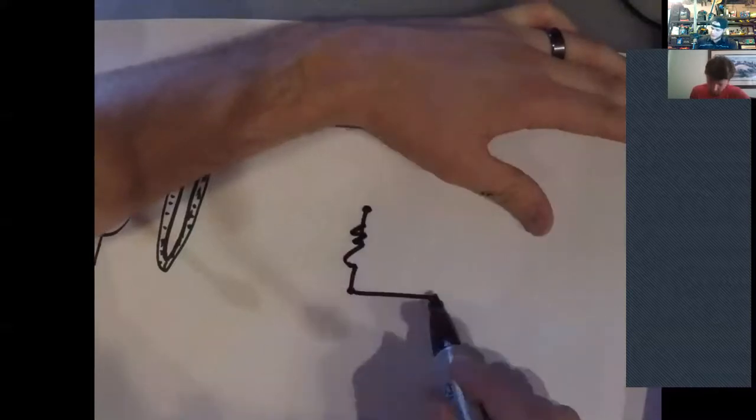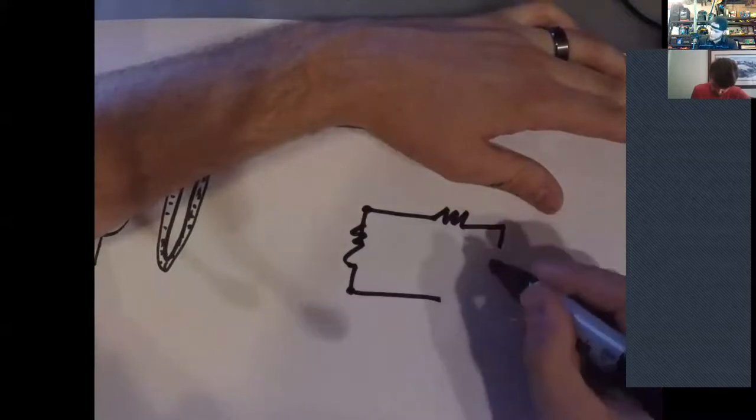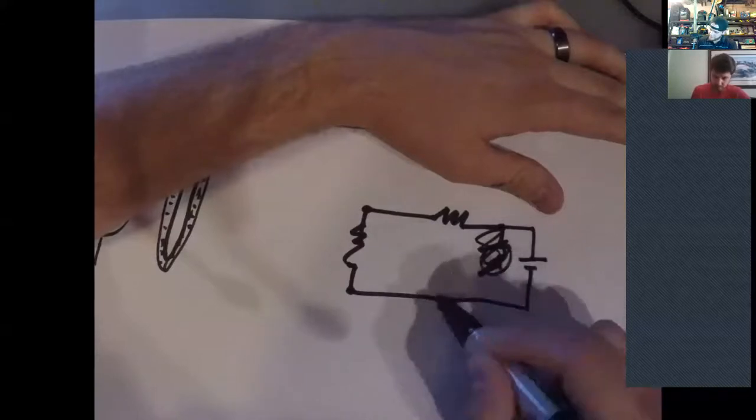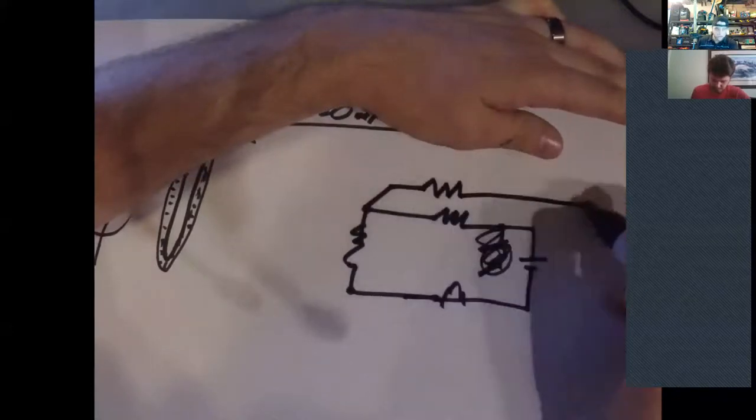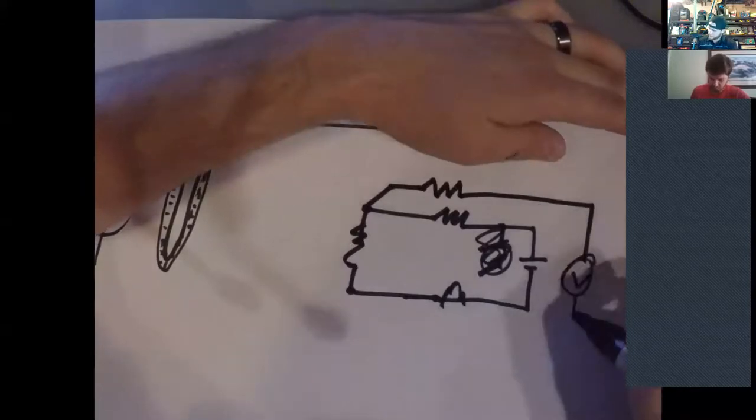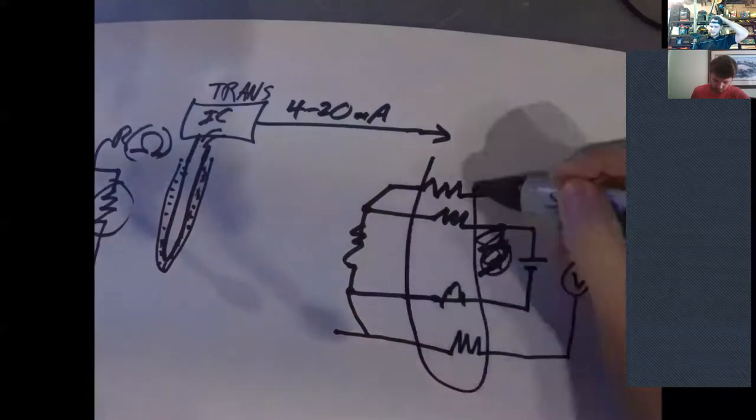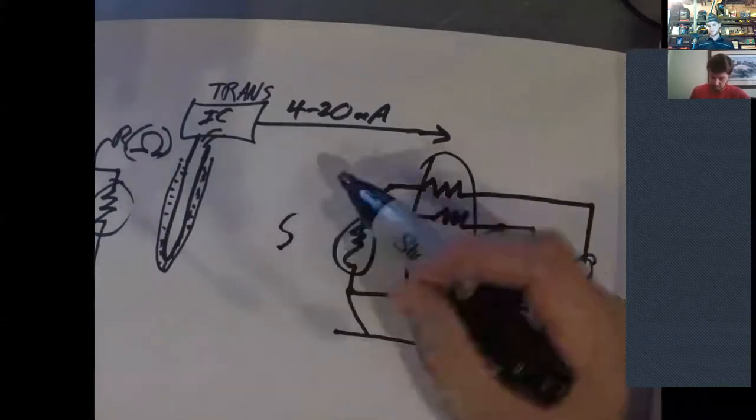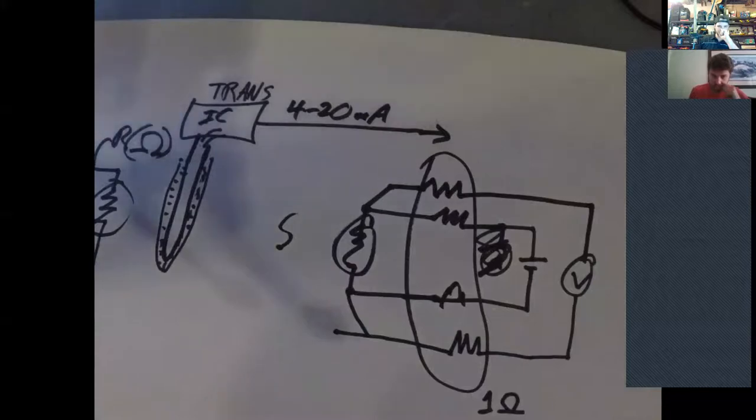Exactly. Voltage drop. So you have an inherent resistance in your wires. And so if your wire length is really long, you actually have to calibrate that into your control system. So you'll have a voltage drop inherent in those wires, but in reality, those wires are just like this resistor where they're sensitive to temperature.